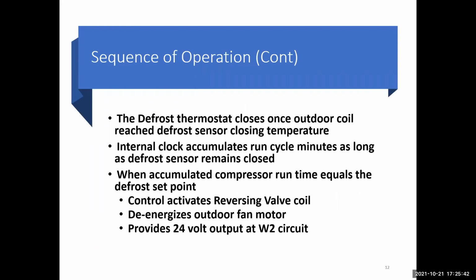The defrost thermostat closes once the outdoor coil reaches defrost sensor closing temperature. Internal clock accumulates the running time as long as the defrost sensor remains closed. When the accumulated compressor runtime equals the defrost set point, the control activates the reversing valve. It de-energizes the fan motor and provides 24 volt output to the W2 supplemental heat circuit.